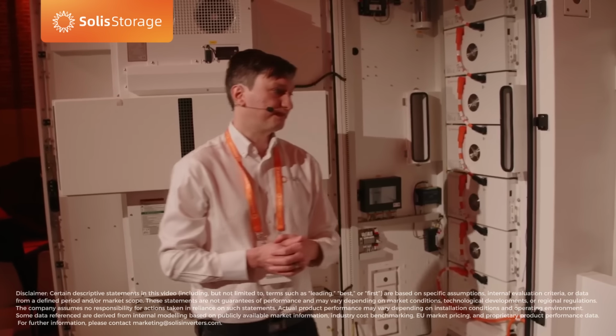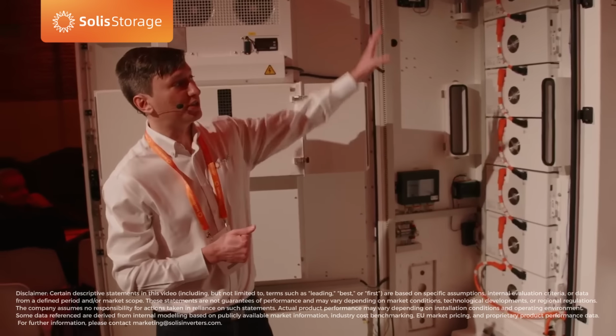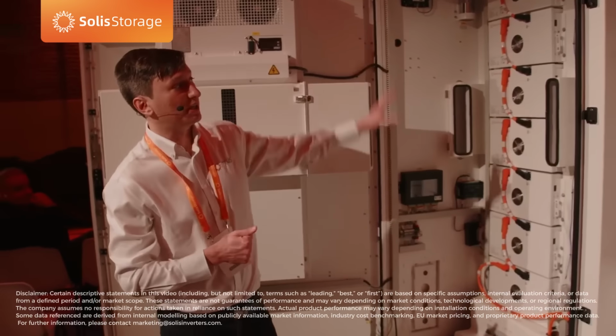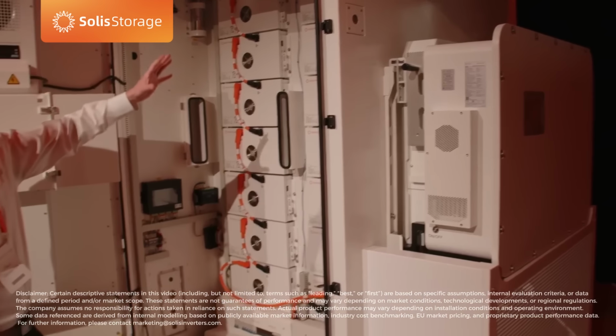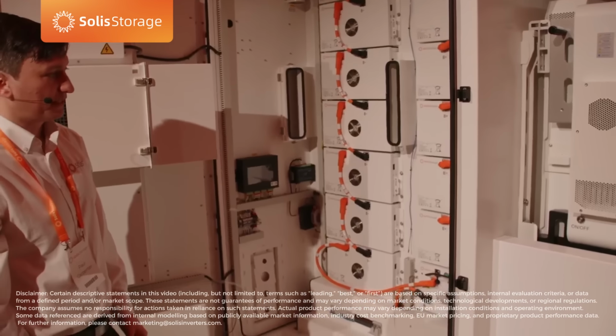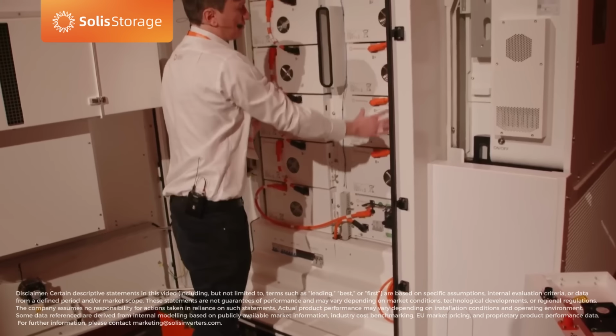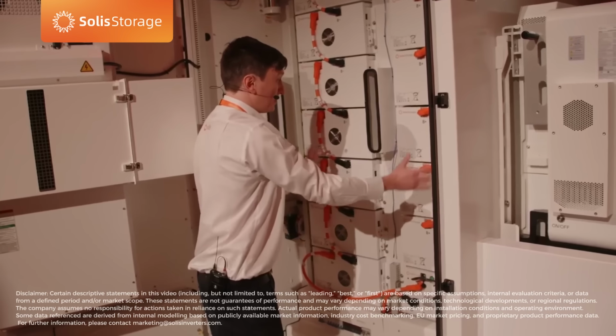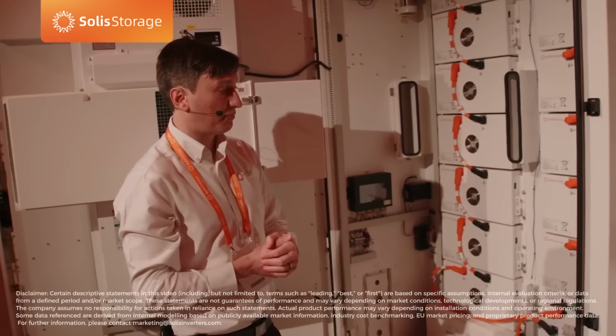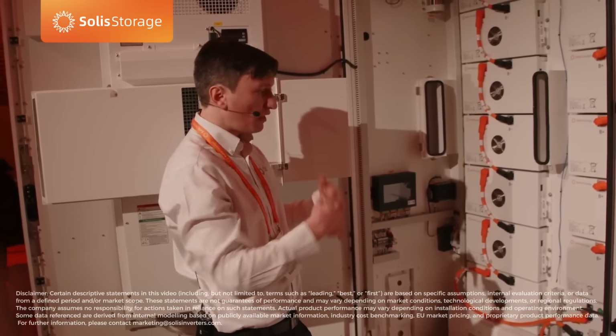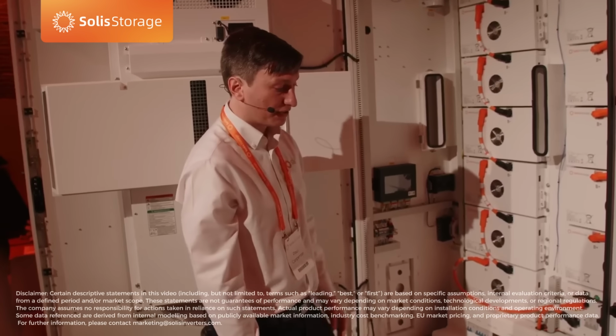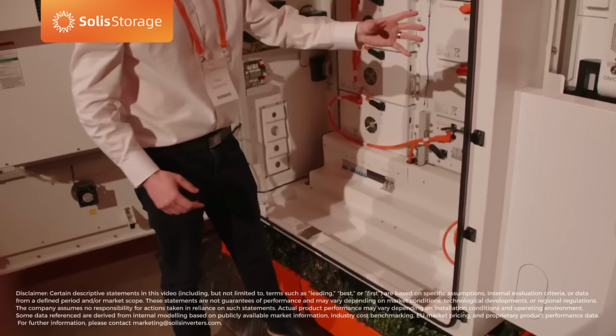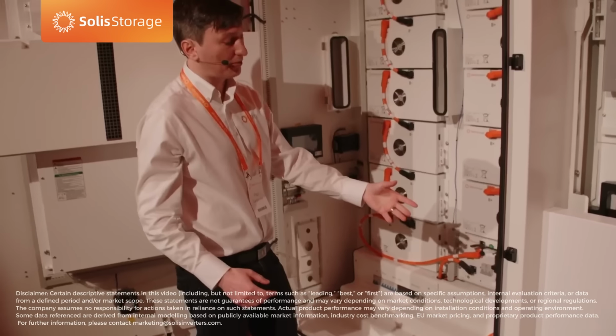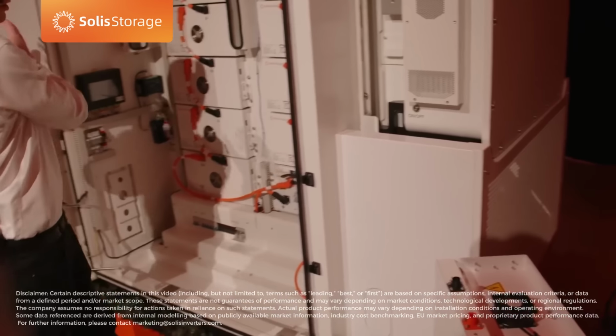One of the other things that Travis spoke about was the structural separation on these units. So we've got the hybrid inverter outside, and we've got our DC battery solution inside. Notice how simple, easy, neat and tidy the wiring is for this cabinet. There's a lot of hidden cables behind the trunkings and these plates, and all of that wiring is done beforehand in our factory in China. So the only wiring the installer actually needs to do at the end of the day is these power cables running through to the hybrid. There's a communication cable running through to the hybrid, and then the hybrid has got a set of 3-phase AC cables running back into the cabinet, powering up our aircon.